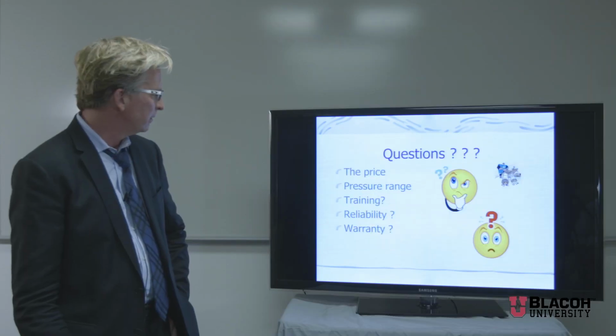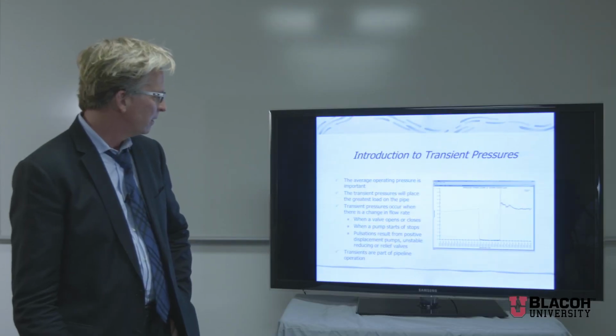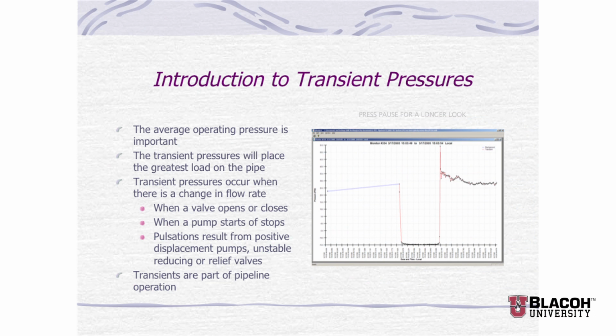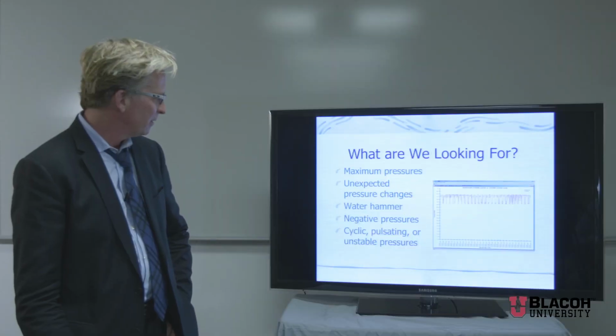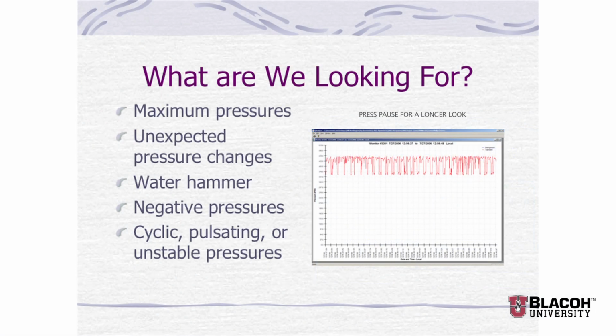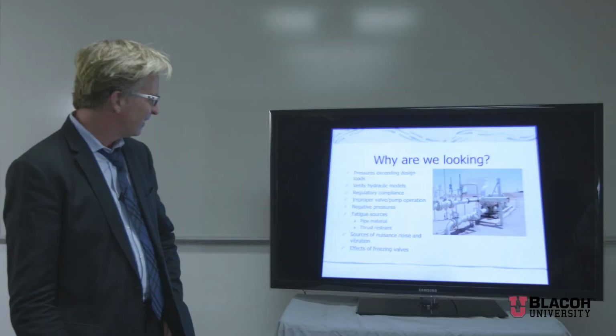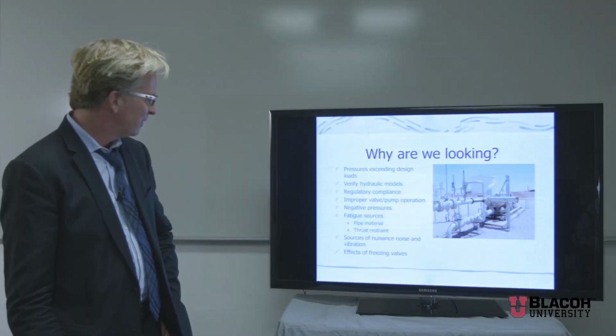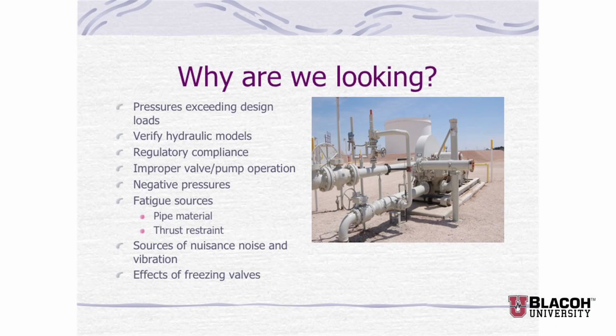Kind of some general. So again, there's a nice recording of a down surge pump trip, with the pressure wave oscillating back. Oscillations in the system. Looks like they need a pulsation dampener with that graph. And again, a lot of applications.